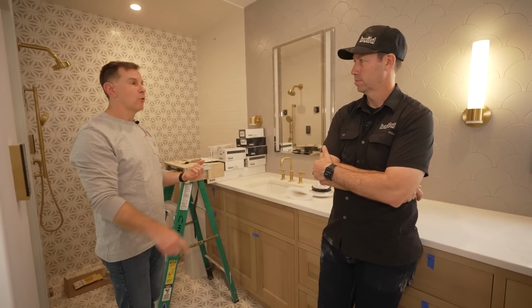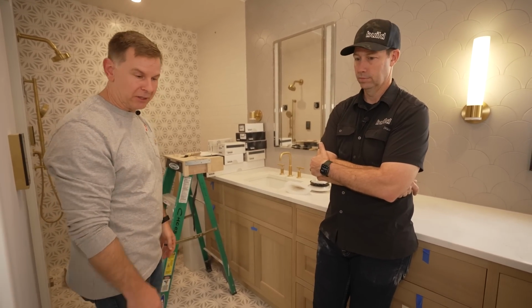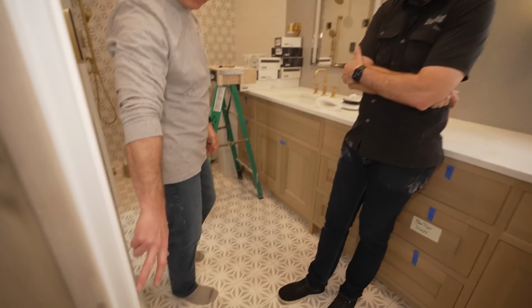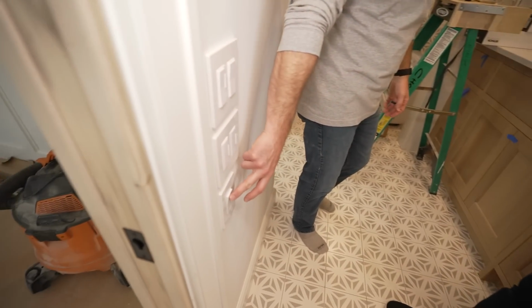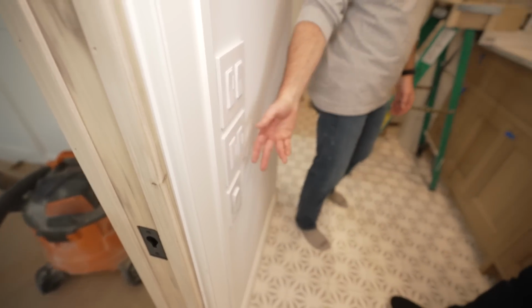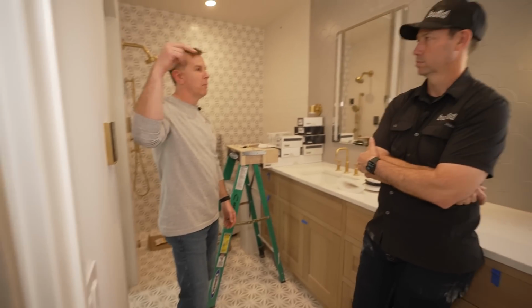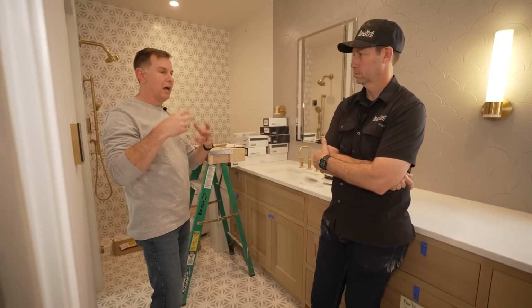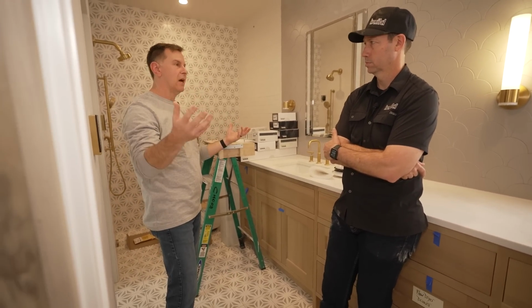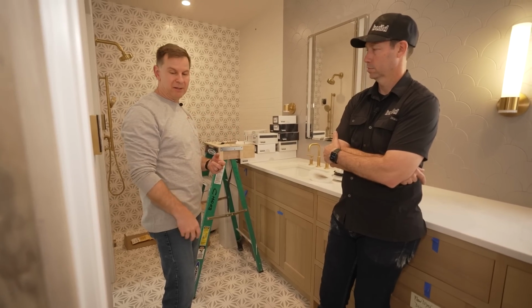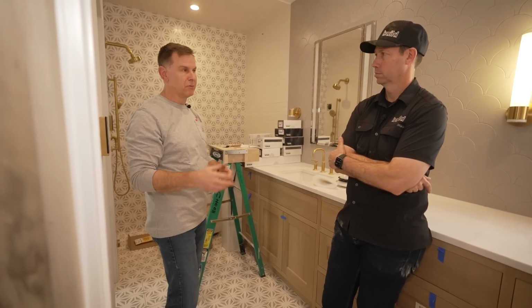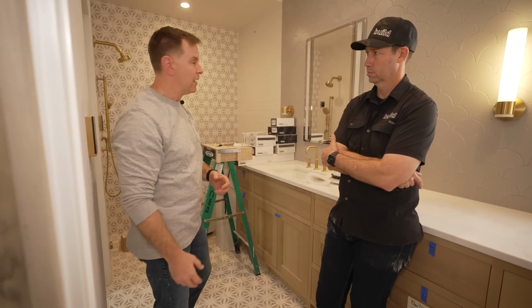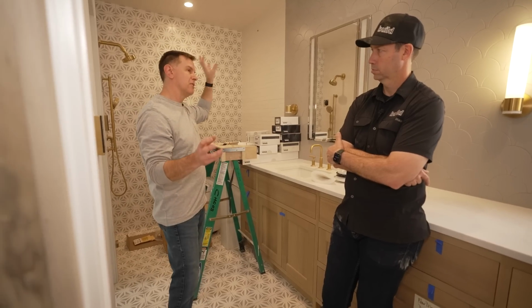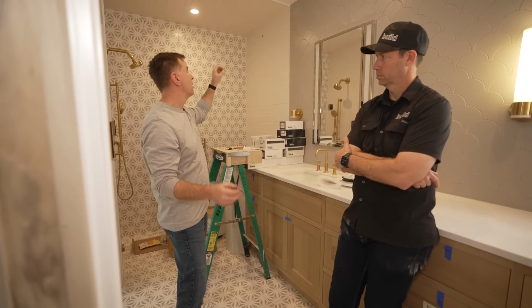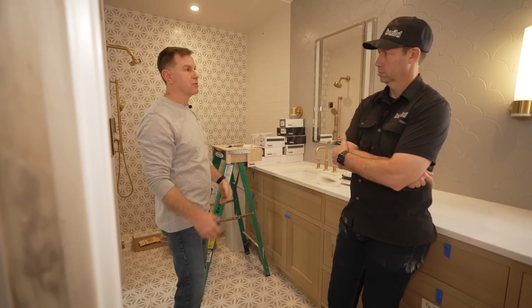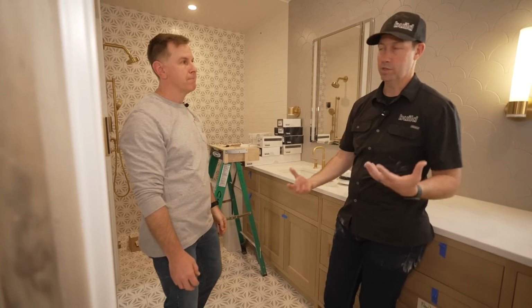But when you're showering or using the bathroom, you want to go into boost mode. We've got a switch right here, you just come in and touch that. That triggers the system, the unit up in the attic, and it goes into high speed, putting the whole system into high speed for a period. The default is 30 minutes, but you can set that to whatever you want. So even though you're normally getting a continuous minimum flow here, you can go into boost mode for showers and things like that, to get all that extra steam out of the room.